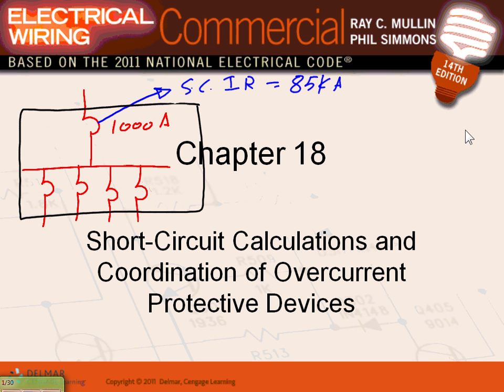Any question, guys, about the interrupting rating? So this means this circuit breaker will be safely able to open up to an 85,000 amp short circuit, be it ground fault, be it single phase to phase, or be it three-phase circuit. So that's the first short circuit rating.